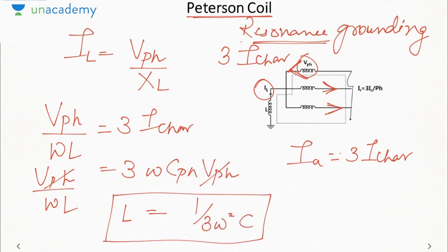This is the inductance that you have to use for the case of resonance grounding or for the case of Peterson coil. This is also called as inductance of the arc suppressor coil, because if you use this inductance, then the line charging current will get cancelled out. There will be no formation of arc. So arc is suppressed here. So it is also called as arc suppressor coil. Inductance of arc suppressor coil is 1 by 3 omega square C. So these are the general methods by which we will ground the neutral of a system. That is, one was solid grounding, other was your resistance grounding, reactance grounding, then Peterson coil. Peterson coil is a special case of reactance grounding in which the inductance is equal to 1 by 3 omega square C.